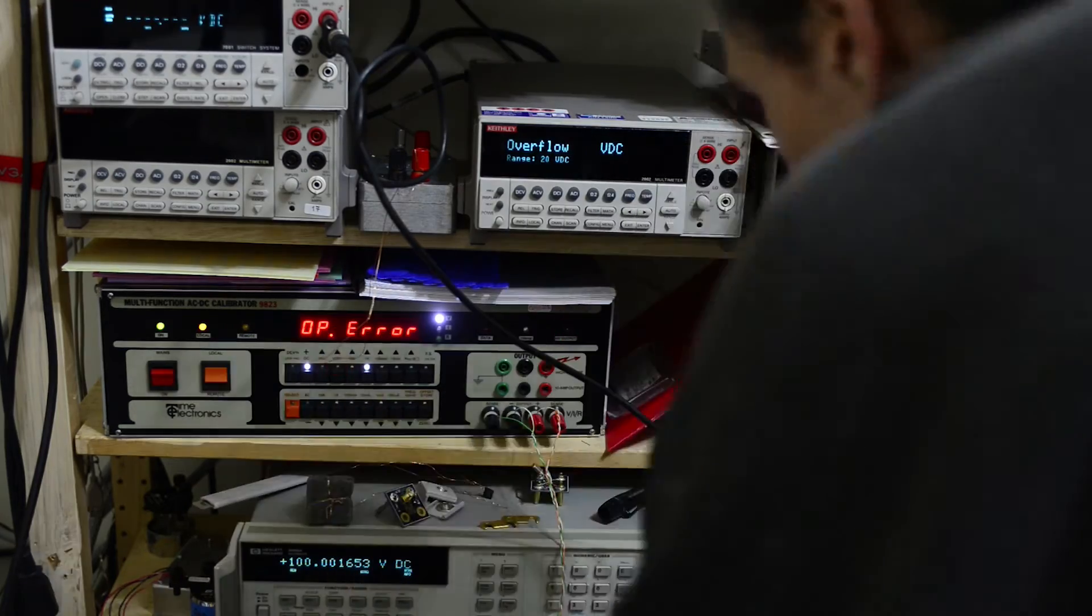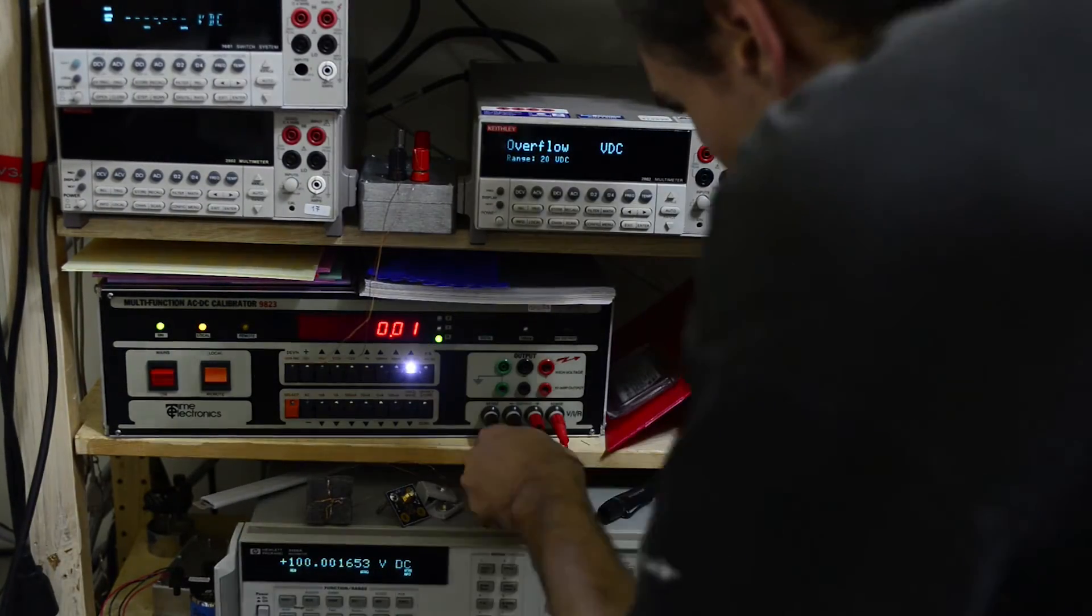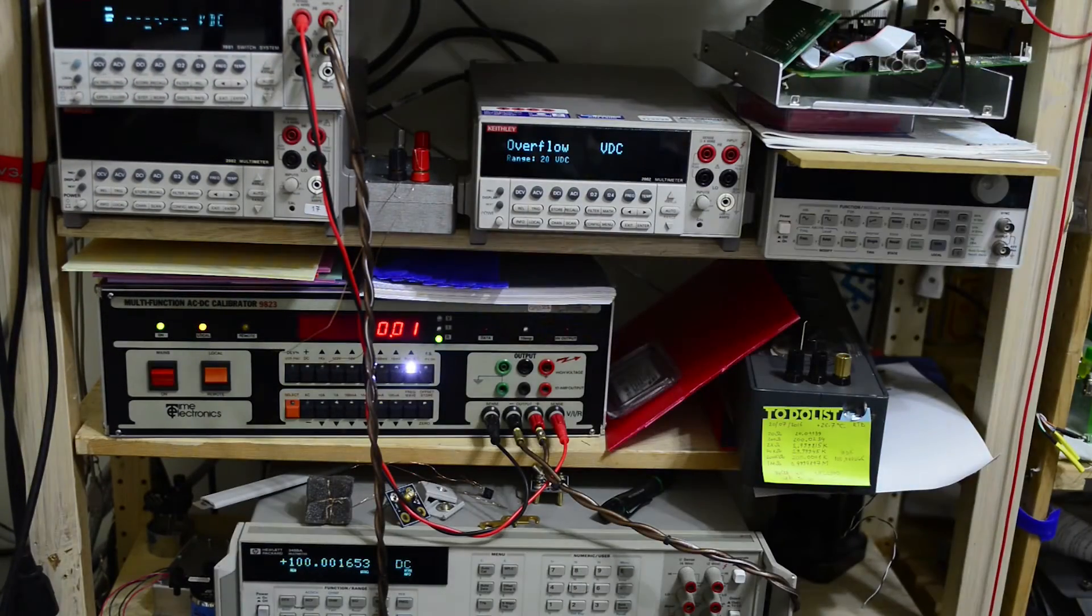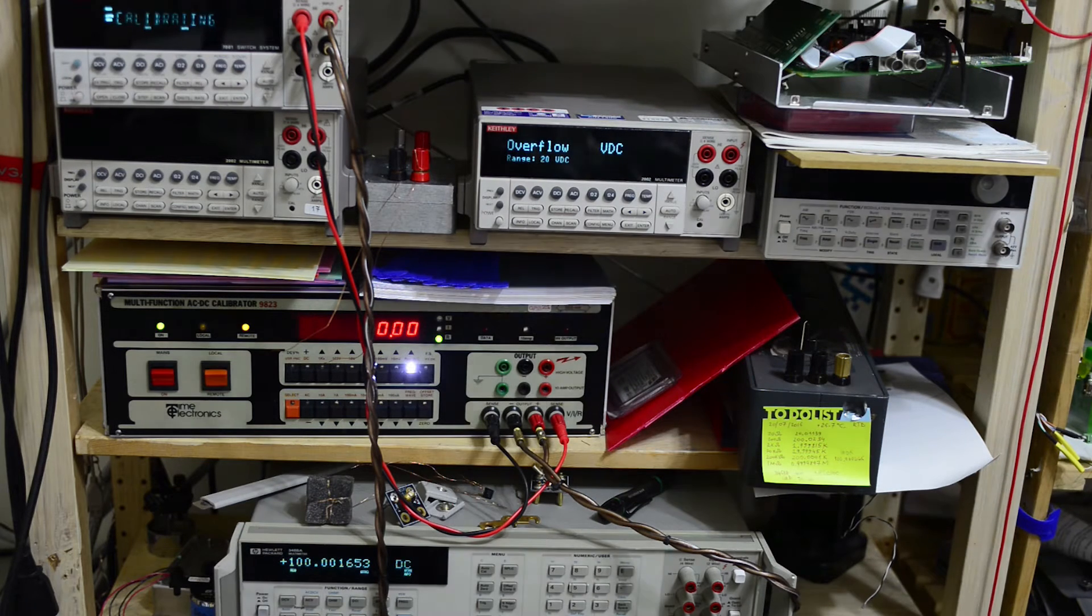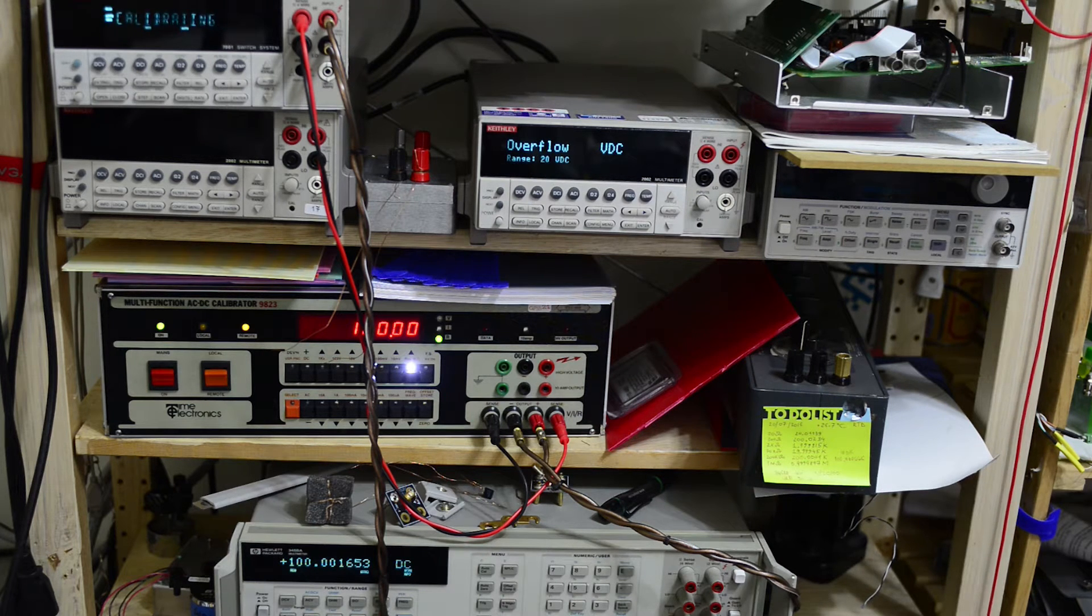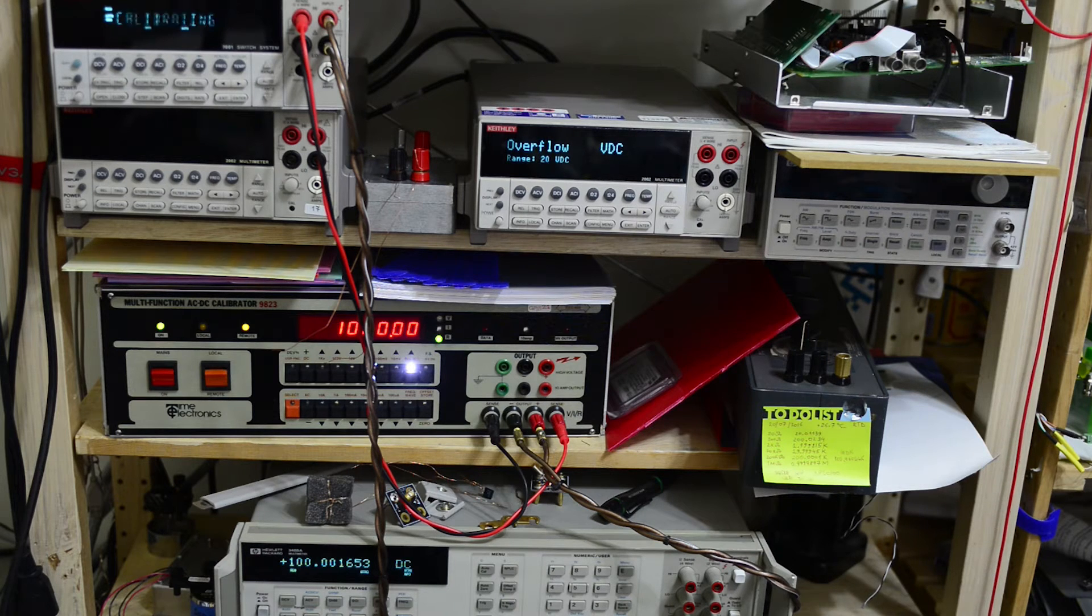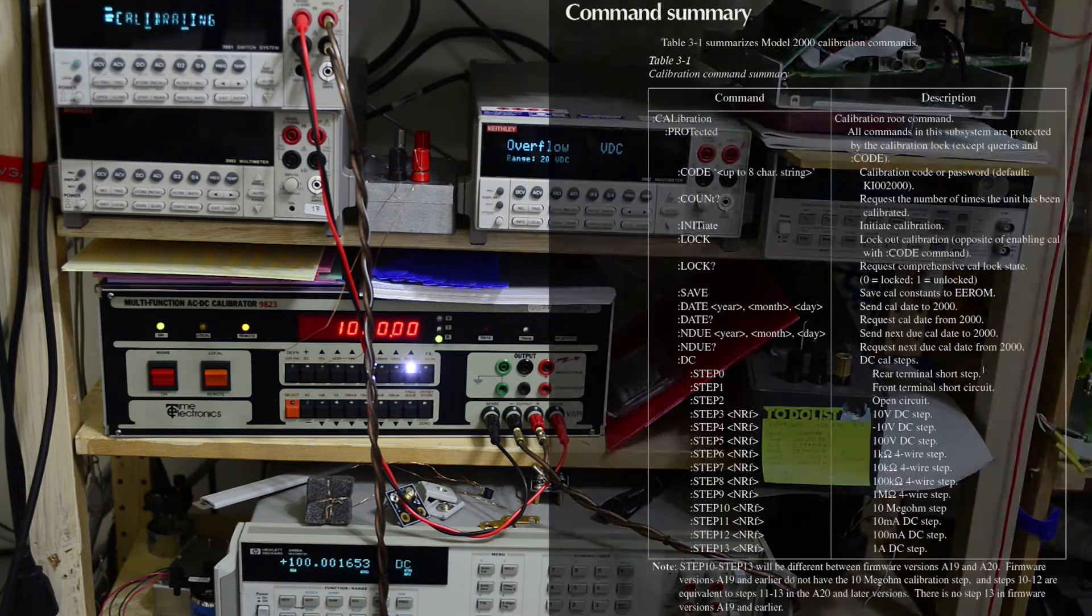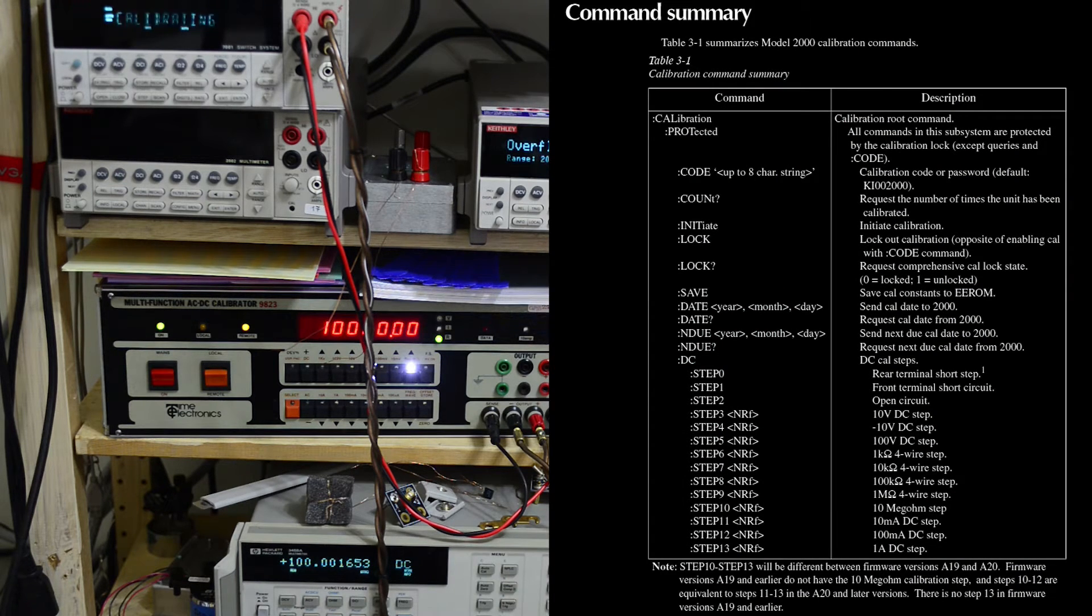And next step is to calibrate resistances using calibrator output and connect four terminals to Keithley DMM. This takes a few minutes, so I'll just show you what the steps are from the calibration manual for Keithley model 2000. Very similar calibration procedures are also for 2001 and 2002 meters, just with different values.